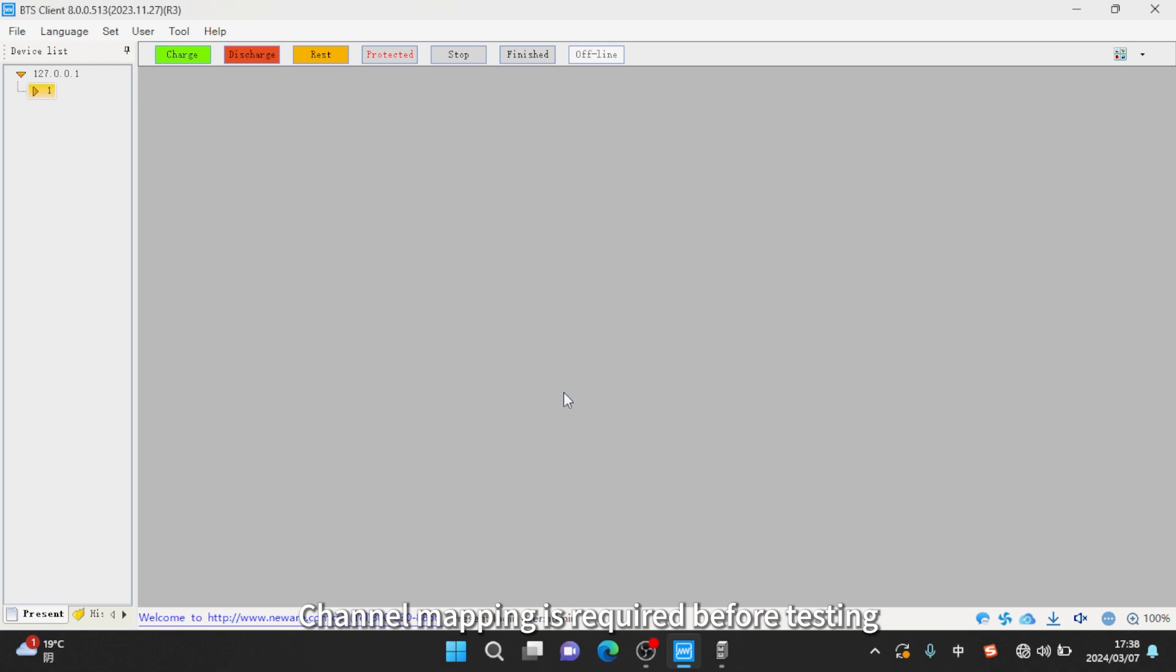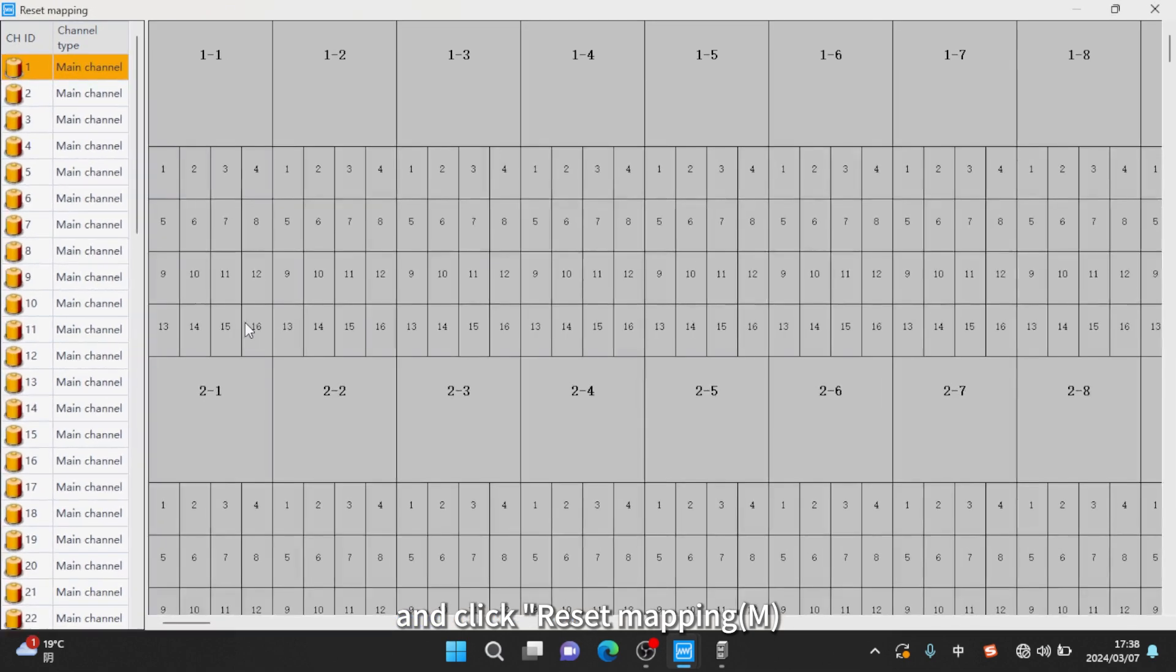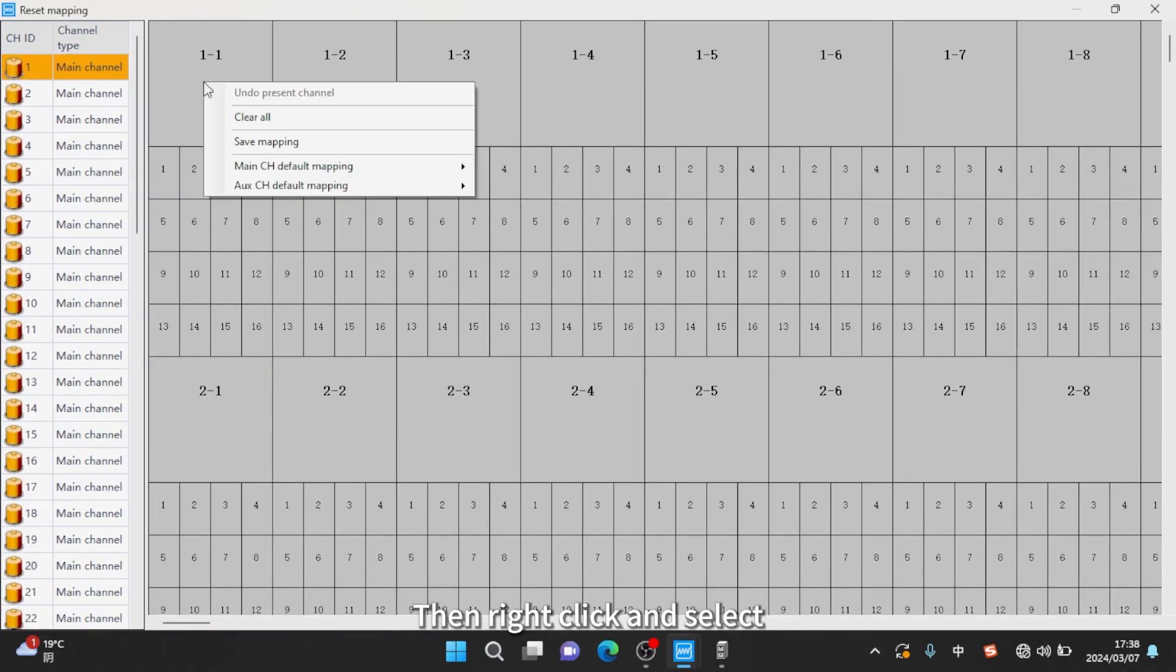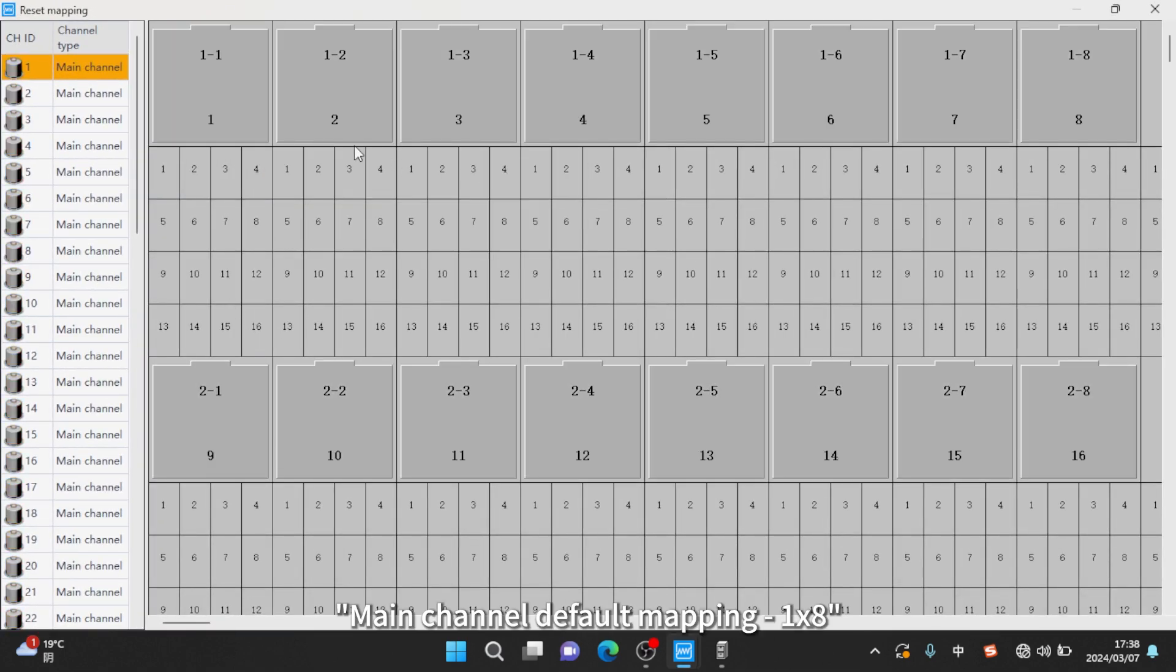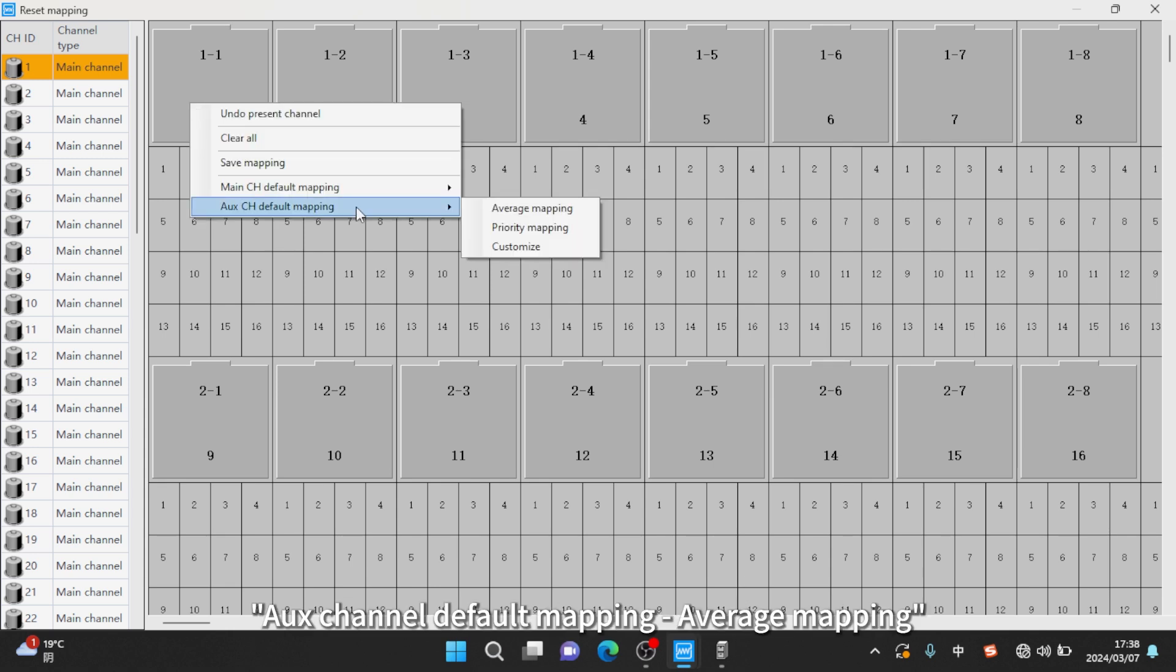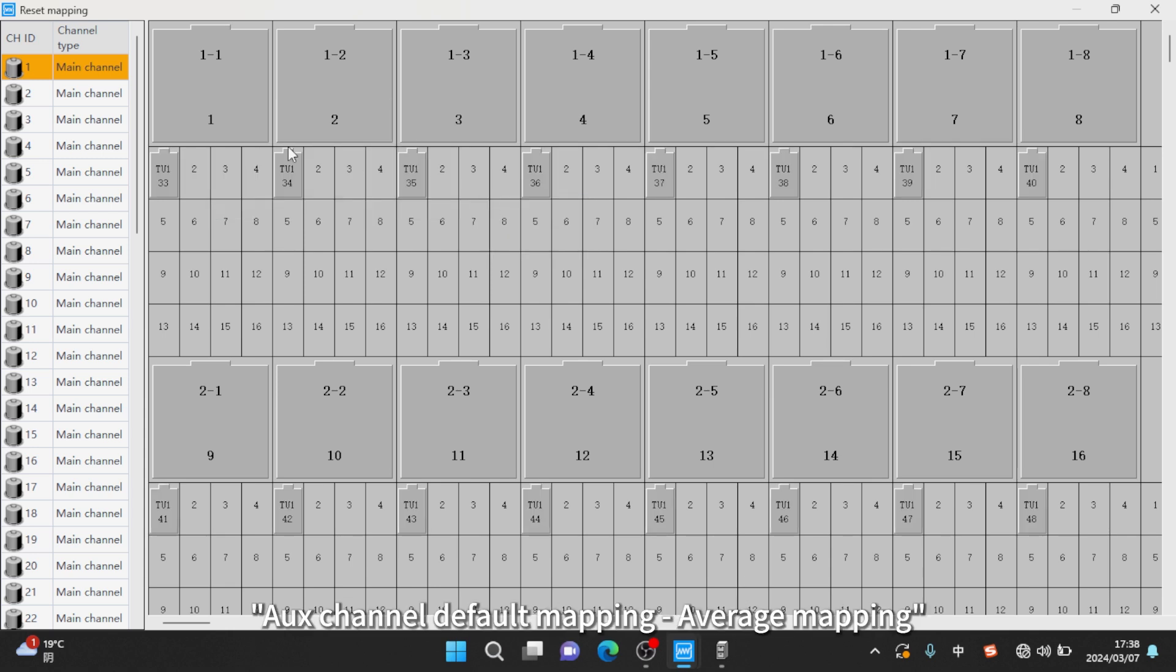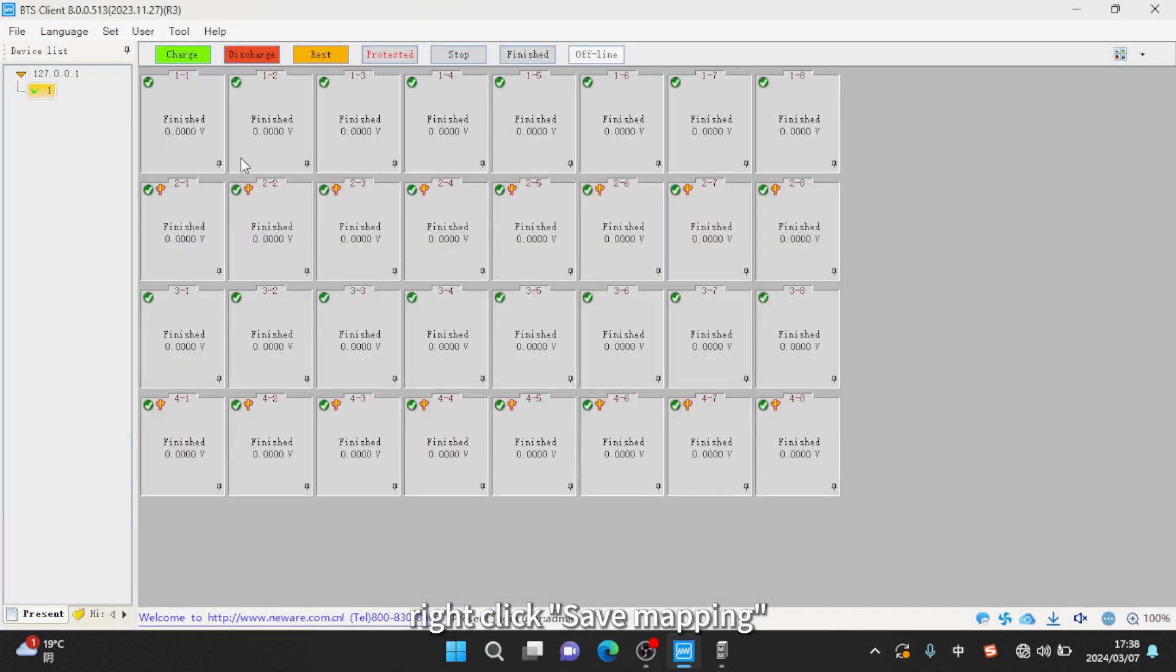Channel mapping is required before testing. Right click on the blank area and click reset mapping M, then right click and select main channel default mapping 1 by 8. Continue right click and select AUX channel default mapping average mapping. Finally right click save mapping.